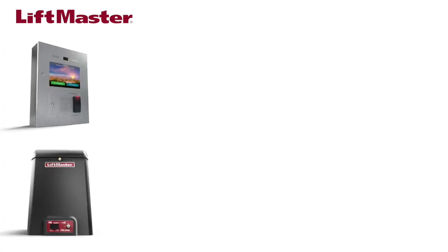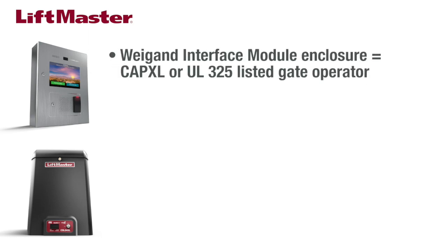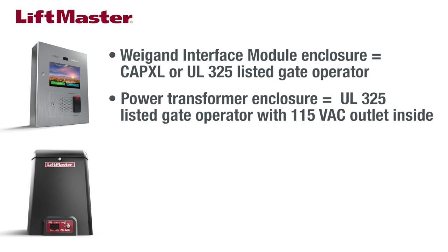To prepare for wiring the LMSC1000, the Wiegand interface module shall be enclosed in a CAP XL access control panel or in a UL325 listed gate operator. The power transformer shall be enclosed in a UL325 listed gate operator that contains a 115 volts AC power outlet.